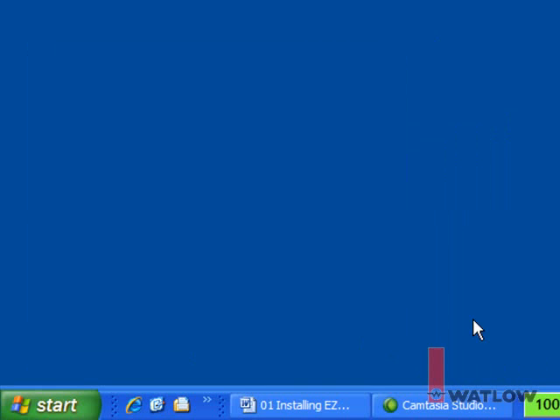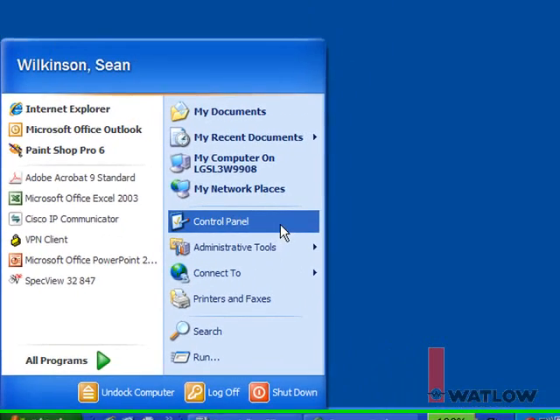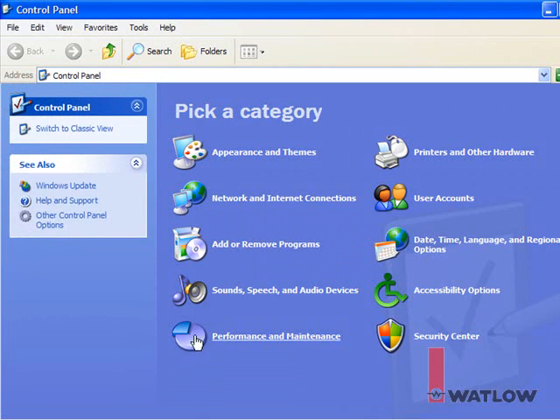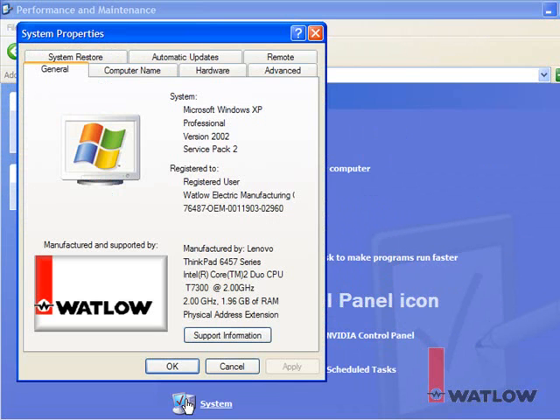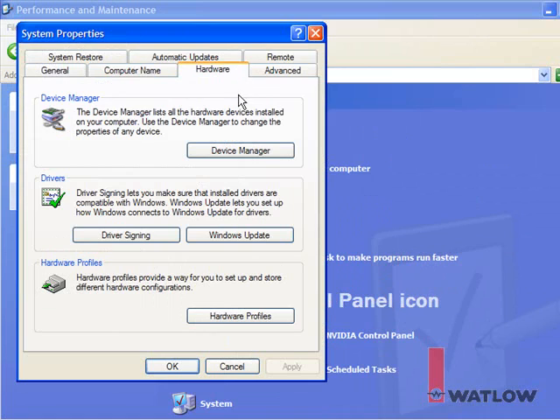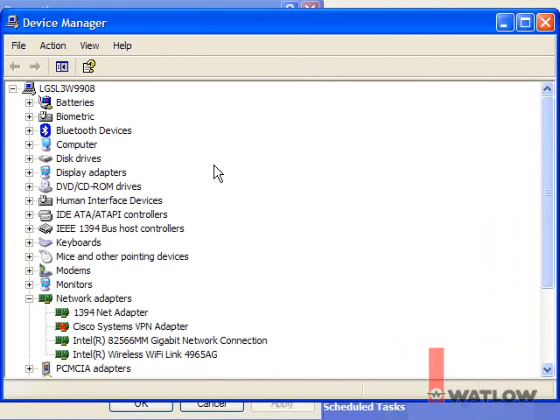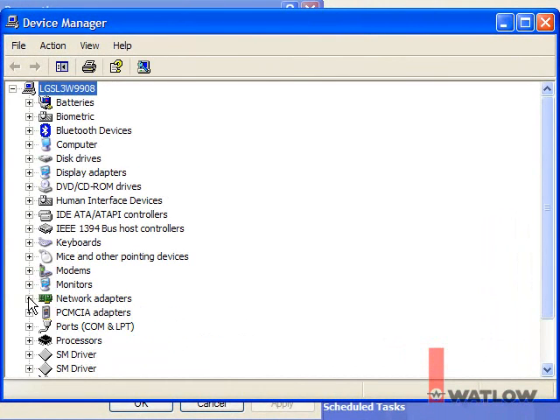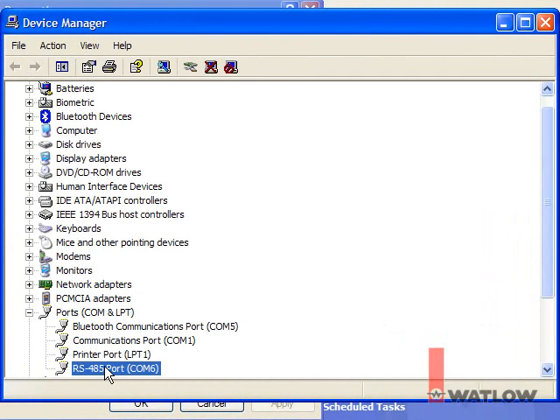To check which COM port number has been assigned and verify that there are no conflicts, click the Start button, click Control Panel, click Performance and Maintenance, click System, select the Hardware tab, click Device Manager, and locate and expand the ports list. The RS-485 port is installed as COM6. If there were any conflicts, Windows would indicate it here.